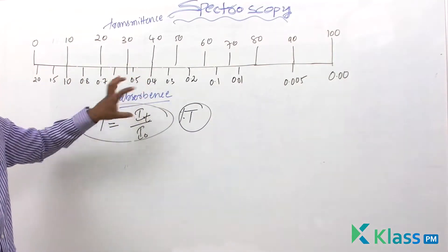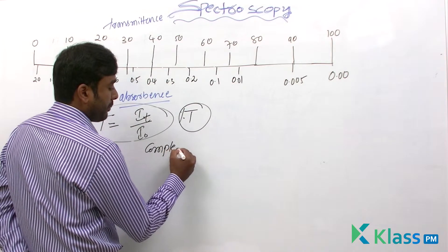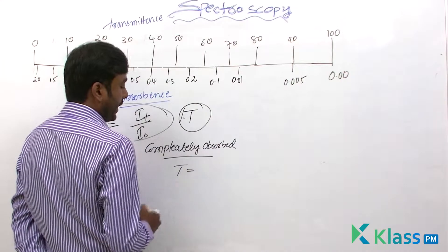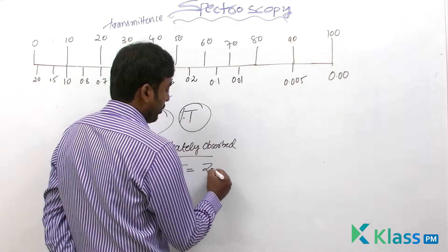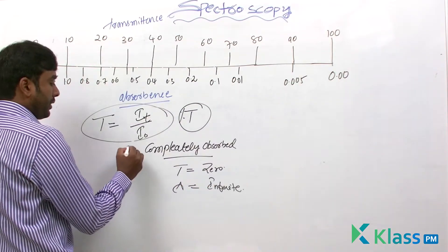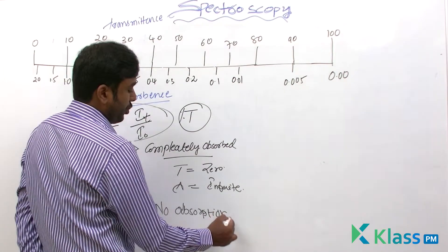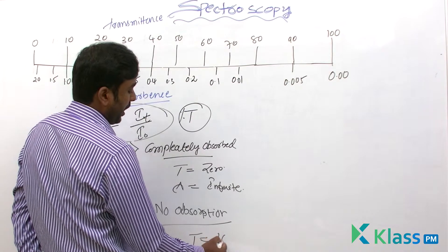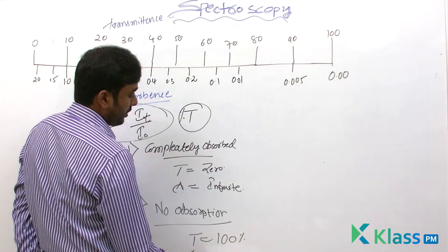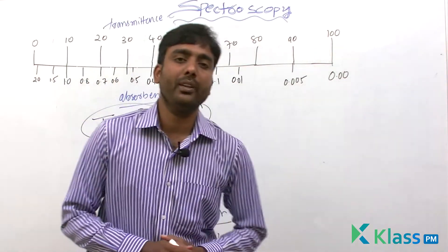This chart shows the relationship between transmittance and absorbance. All spectrophotometers measure absorbance either in terms of absorbance or in terms of transmittance. The transmittance and absorbance relation: if completely absorbed, transmittance is zero and absorbance is infinite. If no absorption, transmittance is 100 percent and absorbance is zero.